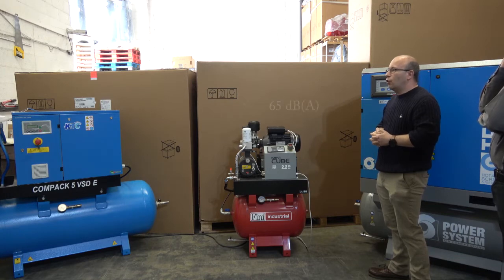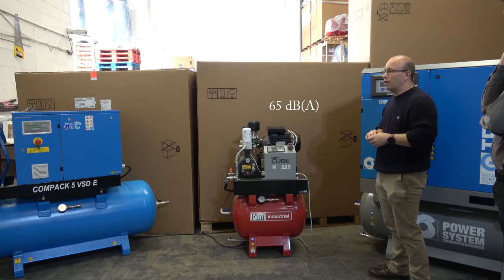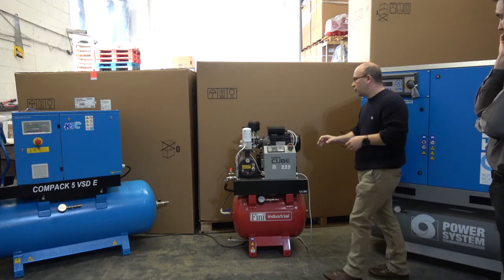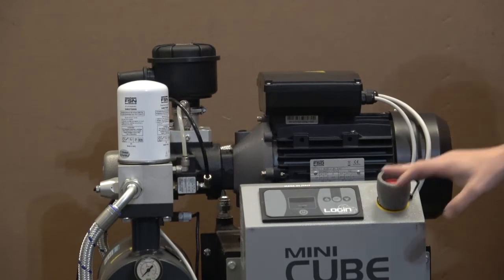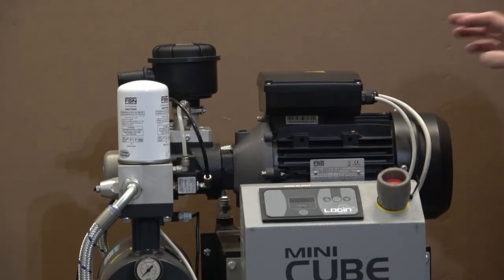On the Hydravanes — the HV02s from memory — I think it was probably about the same sort of noise levels. That's 64 dB, and I think the Hydravane was rated at 65 dB. You've got the benefit of the controller — it gives you service information and you can adjust pressures. The only thing you cannot do with this controller is remote start/stop. There will be a method of doing it on the outgoing side with a valve, but on the controller itself you can't do that. No timer on it either, but that's doable by putting something on the wall.